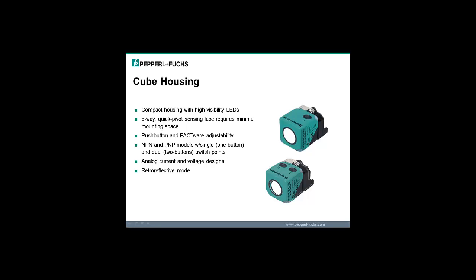The next sensor to discuss is our cube housing. This is a compact housing with, again, very high visibility LEDs on each corner of the bottom and the top rear of the sensing face. So very nice if you're at a distance away and you want to know what the status of the sensor is. You can see it, if it's mounted up high on top of a tank, you can see it from the floor level. The sensing head can rotate in any of 5 different positions, which is very nice. You can program it via the push buttons or PACTware, NPN and PNP models, also analog and current and voltage models. And it offers a retroreflective mode, which is kind of nice for detection of irregularly shaped objects.